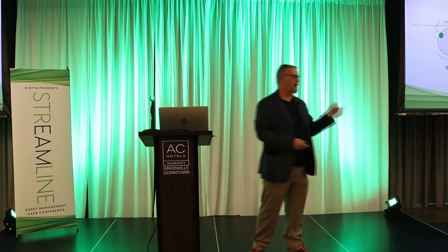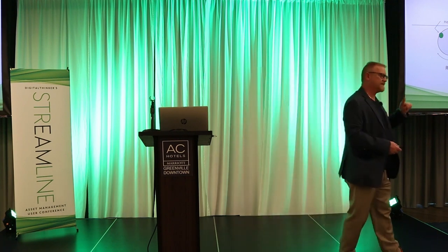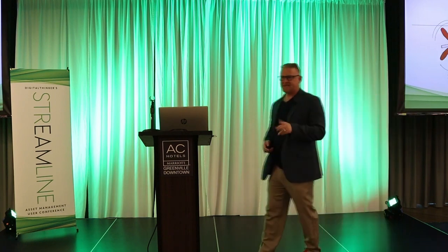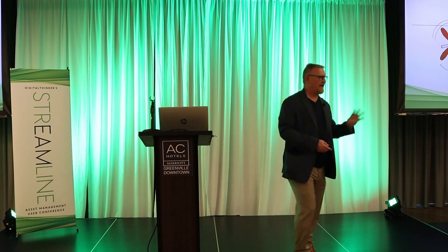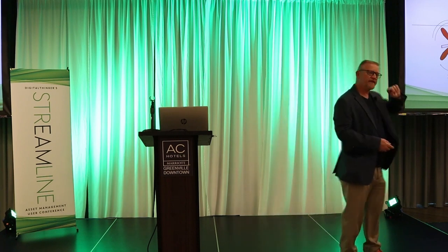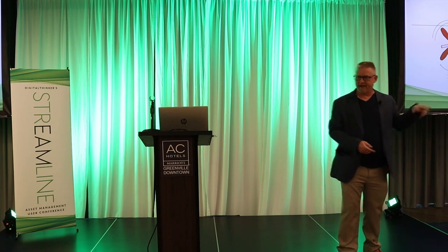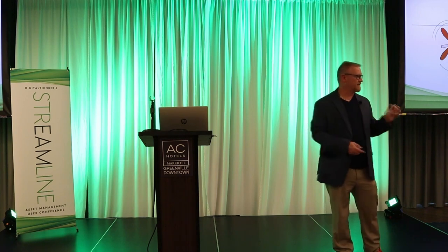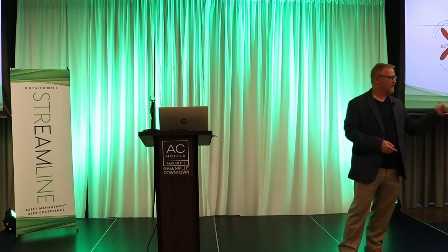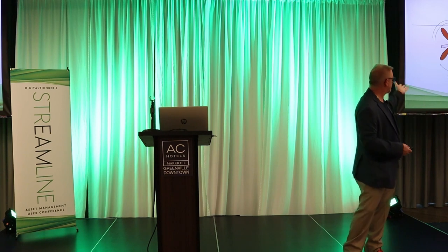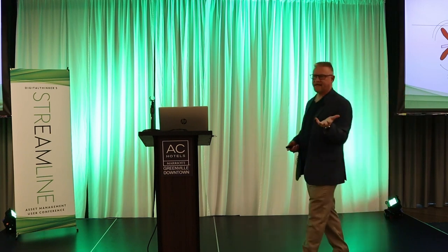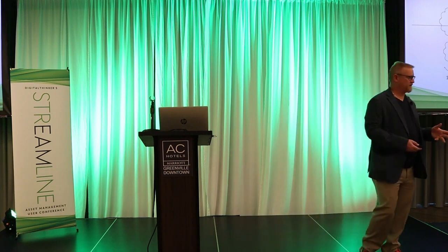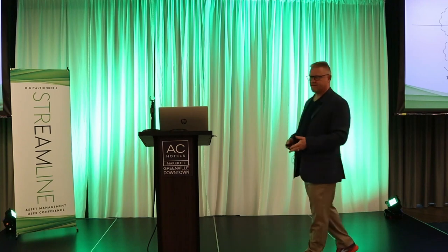This is called 1 times turning speed, or 1 cycle, or 1 order of turning speed. If that shaft has 4 fan blades on it, every time I rotate the shaft, there are 4 sinusoidal waves that occur, 1 for each blade. And they are considered phase locked, meaning they're locked to the shaft. And in this case, because there are 4 and they are equidistant, they are 90 degrees apart. If I have a gear with 12 teeth on that shaft, it has 12 sinusoidal waves.